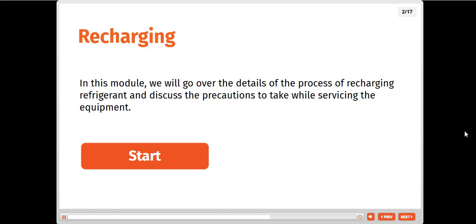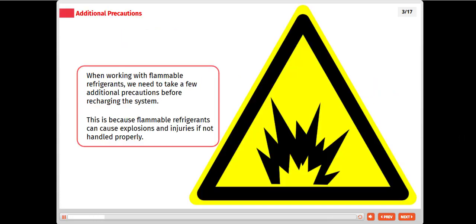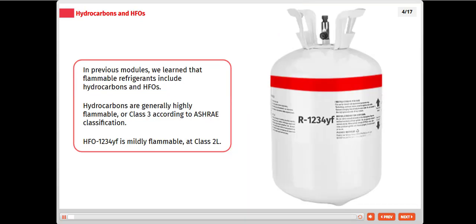When working with flammable refrigerants, we need to take a few additional precautions before recharging the system. This is because flammable refrigerants can cause explosions and injuries if not handled properly. In previous modules, we learned that flammable refrigerants include hydrocarbons and HFOs. Hydrocarbons are generally highly flammable, or Class 3 according to ASHRAE classification. HFO 1234yf is mildly flammable, at Class 2L.